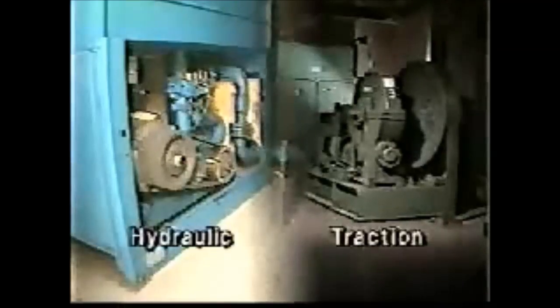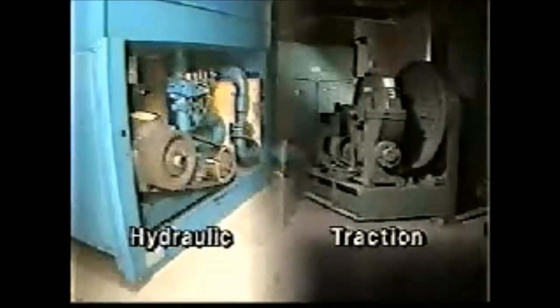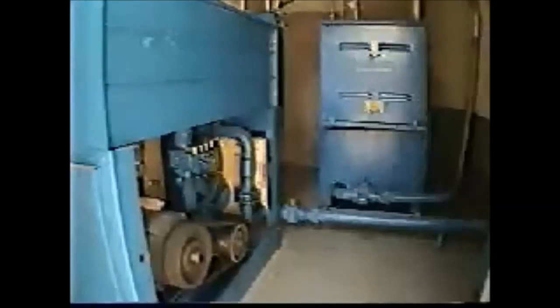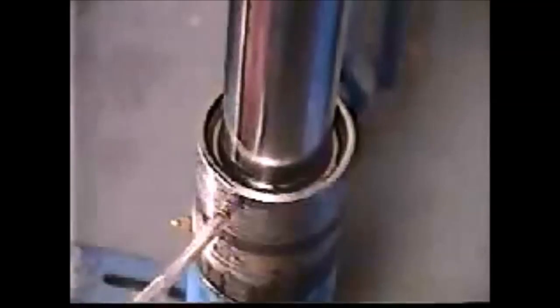There are two types of elevators, hydraulic and traction. The hydraulic elevator usually serves a few floors, with low stops and travel speeds of up to 200 feet per minute. Traction elevators are designed for taller buildings and can travel at much higher speeds. Hydraulic elevators are pushed up from underneath, while traction elevators are pulled up from above. A jack is required to push the hydraulic elevator up.